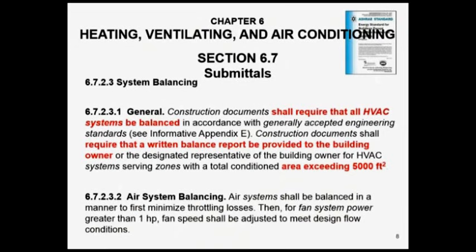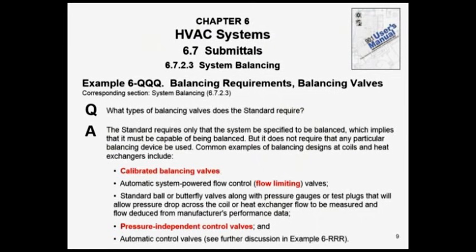And if you had a hydronic system in a building of that size, you'd have to have a balance done. And read a little bit further, the report has to be turned over to the building owner. So you engineers listening are going to have a balancing procedure in your specification. You're going to provide instrumentation for that, and it's got to be instructed that this balancing report is turned over to the owner in order to meet ASHRAE 90.1.